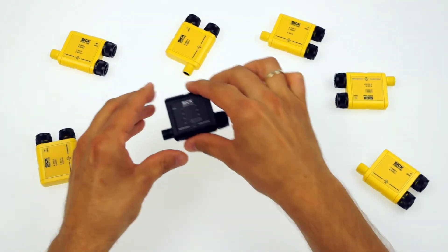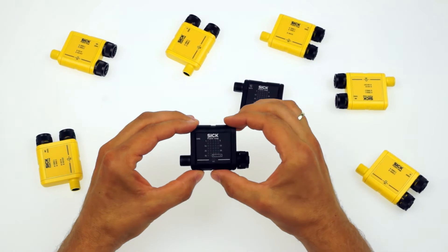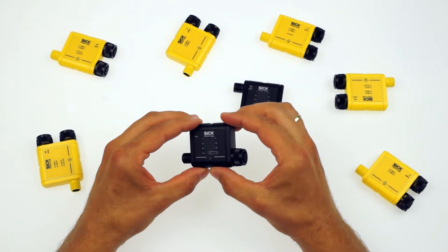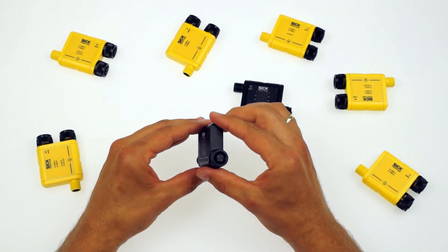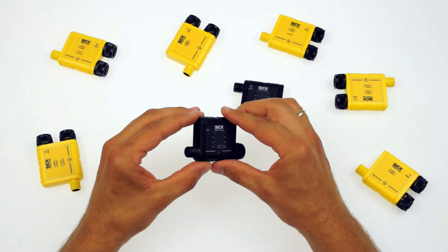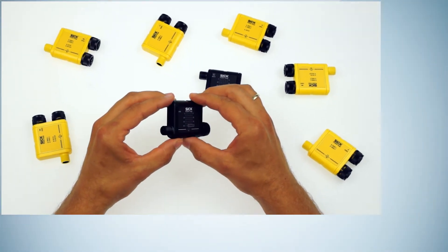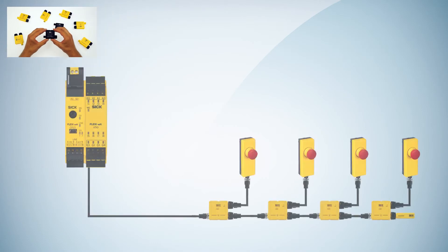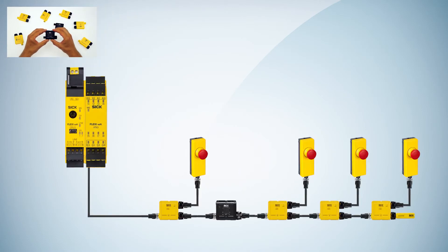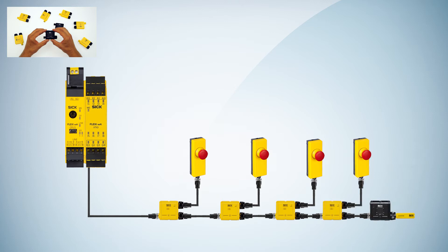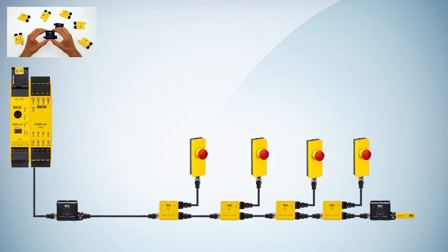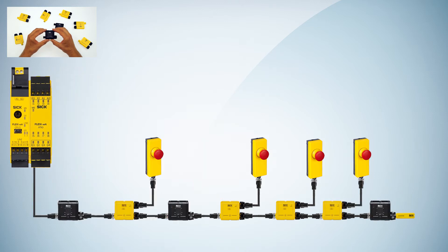Let me tell you more about the diagnostic node. There's a five-pin M12 standard connector on each side, so the diagnostic node can be placed at any position within a FlexiLoop cascade. You can also place as many diagnostic nodes as you like in each cascade, in addition to the 32 FlexiLoop nodes.